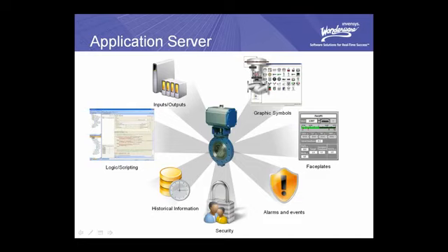Now, with that being said, it is important to point out that Application Server is not the visualization system. It's not an HMI. Rather, Application Server enables you to separate the logical execution of your supervisory system from the visual system while still containing those visual representations. That's one of the key benefits of Application Server, because by separating these functions, the supervision from the visualization, we're able to simplify the design of each component by focusing each on what it's supposed to do, not mixing them all together.